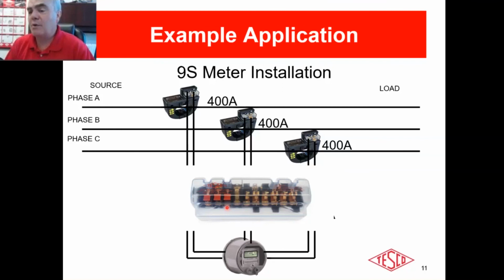If you understand how to utilize the test switches in your service territory, you understand your color coding and how you use them, whether you use reverse potentials or not, you can operate those test switches very safely, and you can work with those commercial industrial accounts very safely. You can test them. You can do things without interfering with the customer or blowing up a transformer, or doing anything else catastrophic. So utilities have maintained that infrastructure, and we continue using a knife blade switch. Even though knife blade switches are out of vogue for almost 100 years, we continue to use them because it's a safe and secure application in this case.